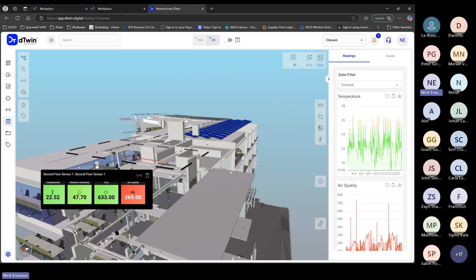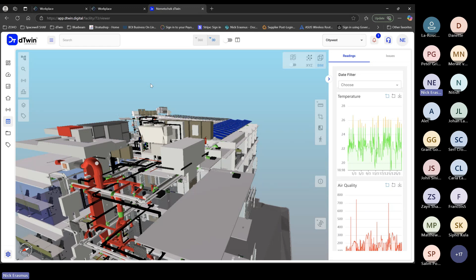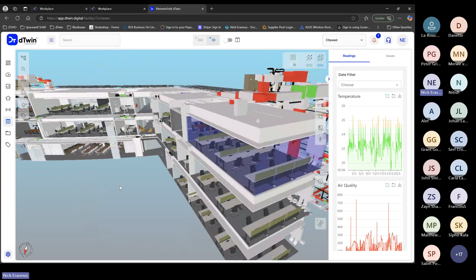Currently the temperature is 22.5, you've got a humidity of 47, your CO2 is 633, but you can see the air quality is not great. There's not enough airflow going through that room, so eventually you'll see your CO2 starting to become a problem because the air gets stale. It's not healthy, and it's not to say it will, but it's an actionable environment. It can actually trigger a sensor notification to one of the senior staff members saying, go open up a window, or hey guys, cool the room down a little bit because you're going to fall asleep here, because the data is telling us there's not enough flow coming through this room. Or it could be something wrong with the HVAC system. So it's all of these things that gives us the power within the digital twin environment to really know where we're dealing with.